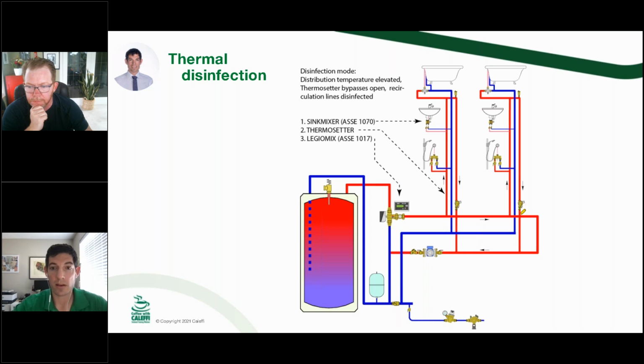So now what we need to do is balance that. There are a lot of different balancing valves on the market, and this one in the diagram is important to make sure, I'll cover it at the end, that we're getting that proper temperature to all of those risers. So this valve has a knob on the top that you set to a temperature. You could say, I want the return from that riser to hit 130 degrees. Or in disinfection mode, we actually open a second orifice and it lets up to 160 or 140 through that cartridge to make sure that we're not just disinfecting the path of least resistance, but we're disinfecting all of the risers, with the balancing valve playing traffic cop to make sure that hot water goes where it's supposed to, to disinfect the largest volume of water and the biggest amount of branches as possible.